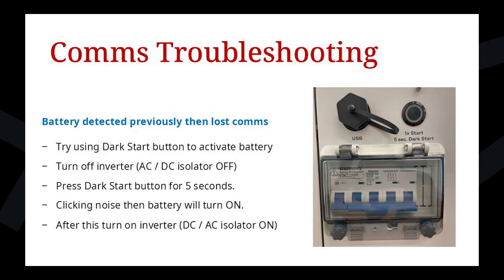If you have a situation where the battery was detected previously, so communication was fine, and then you lost the comms afterwards, what you can try to do is use the dark start button to activate the battery. So first, turn off the inverter, so AC isolator, then DC isolator, and then press the dark start button for about 5 seconds, and you should hear a clicking noise, and then the battery will turn on. After this, turn on the inverter, AC and DC isolator, and then essentially, yeah, hopefully the communication will be working.